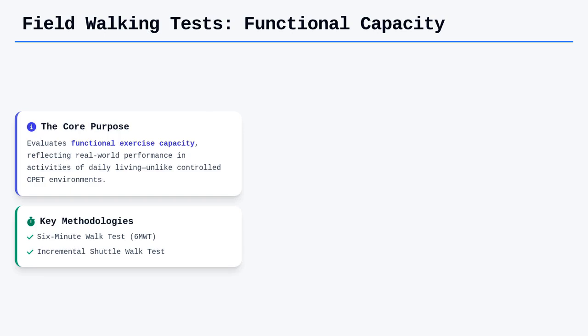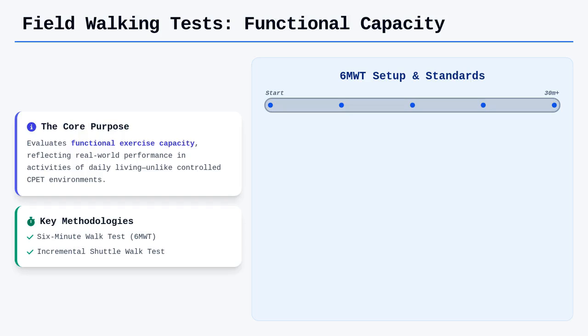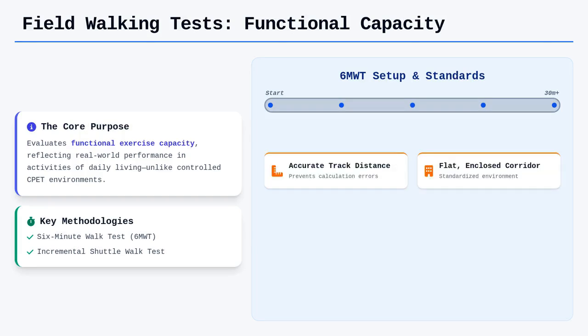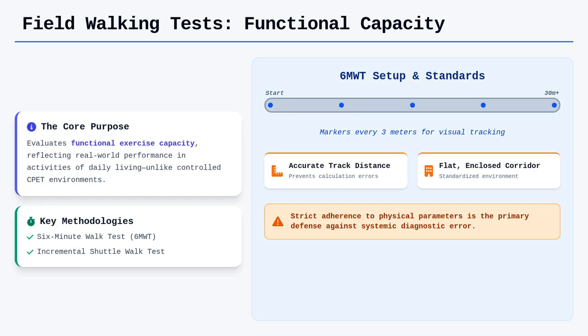Unlike controlled cardiopulmonary exercise testing, these field tests reflect how a patient performs during activities of daily living. The 6MWT is a submaximal exercise test that provides a surrogate measure of endurance, typically conducted in a flat, enclosed corridor of at least 30 meters in length. You must ensure the course is measured accurately, as improper track distances directly invalidate the final distance calculation. Markers placed every 3 meters serve as clear visual aids for both the technologist and the patient to track progress during the walk. Consistent application of these physical parameters is the primary defense against systemic error in your diagnostic reporting.